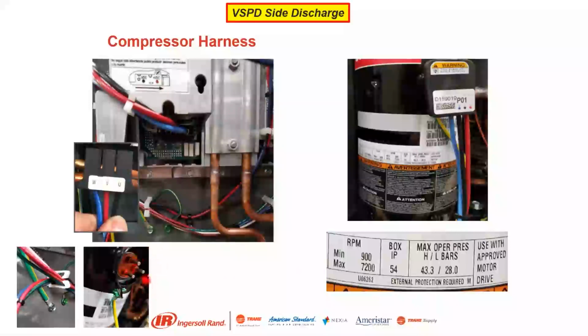When we're testing compressor resistance with the power off, we're going to take our readings right at the compressor. We're also possibly going to test the harness. So that does pull right off, again, with the voltage off, with the disconnect off, and wait a couple minutes for the power to subside. Those capacitors in this drive do store power. So even with the power freshly disconnected, it is possible shock.